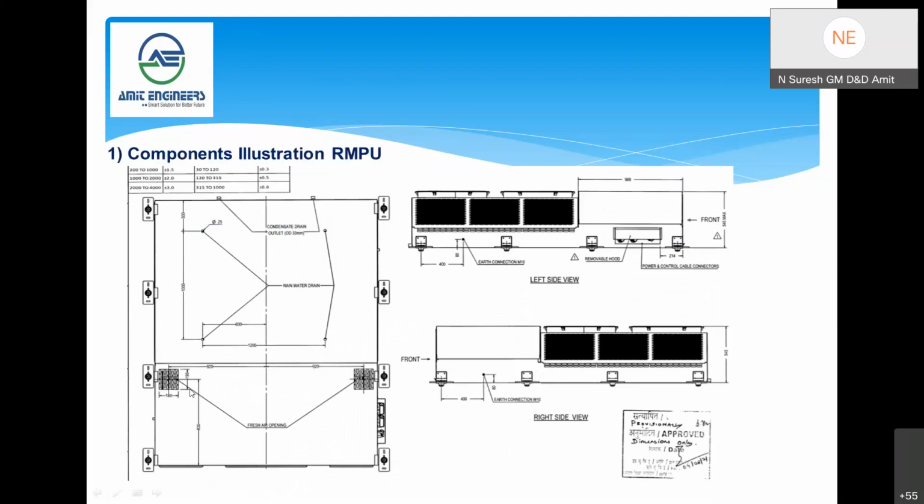So this is to have more clarity. This is the bottom view of the unit, showing the fresh air intakes. And other than the condensed water drain hole, in the condenser area also, water has to drain in the rainy season. There are four drain holes. The inside view gives some idea about the mountings. There are four mountings on each side, so 8 mountings per unit. And in the Train 18 HVAC, the power and control connectors are on one side. All the three quick connectors are placed on one side of the unit.